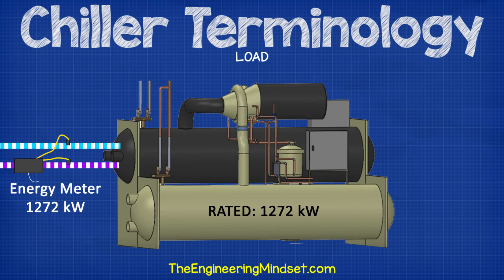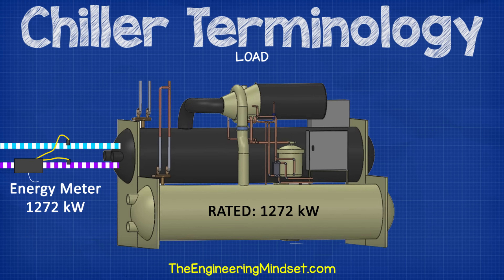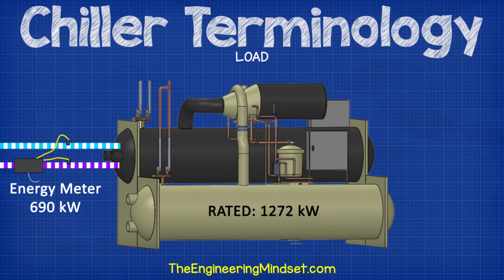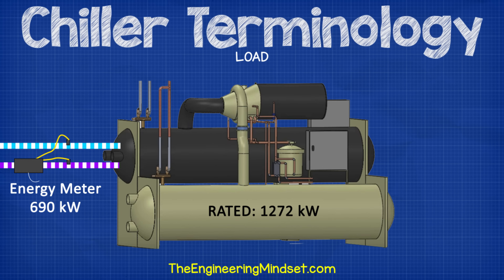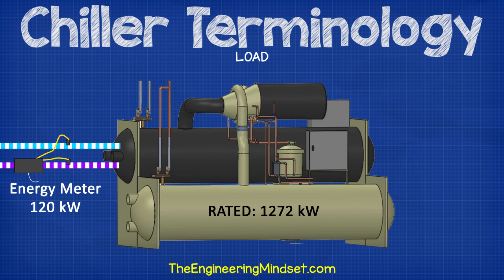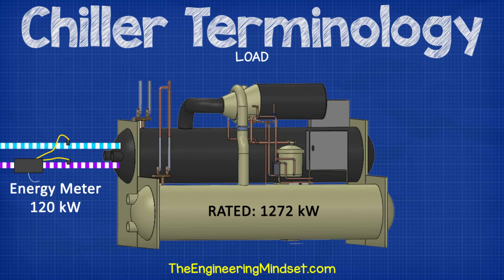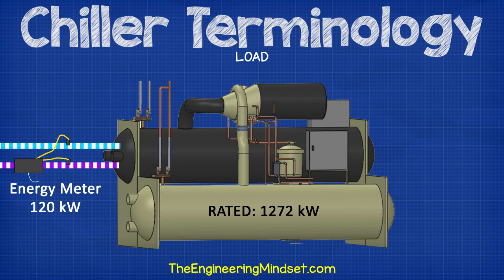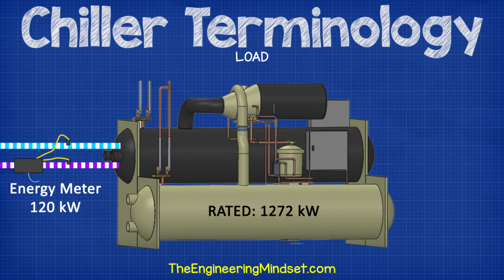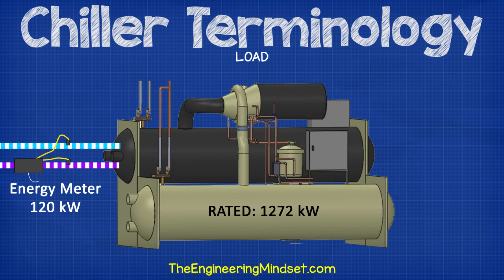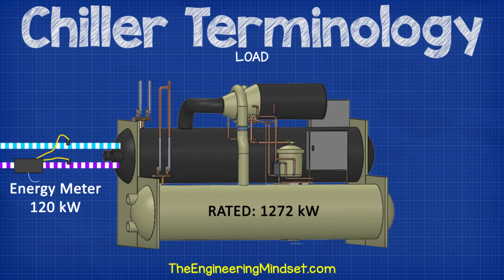Load. Load refers to the cooling demand on the chiller. Full load means that the chiller is operating at its maximum cooling capability, but this is only for around 1–2% of the year typically. Part load means the chiller is operating at less than its maximum capability — this is normal for most of the year. Low load means that the chiller is operating at very low capacity. Faults can often occur at these conditions, and chillers typically do not operate very efficiently at low load. If a chiller is operating at low load for long periods throughout the year, it is likely oversized and alternative options should be investigated. Cooling load is typically measured in BTUs, refrigeration tons, or kilowatts.